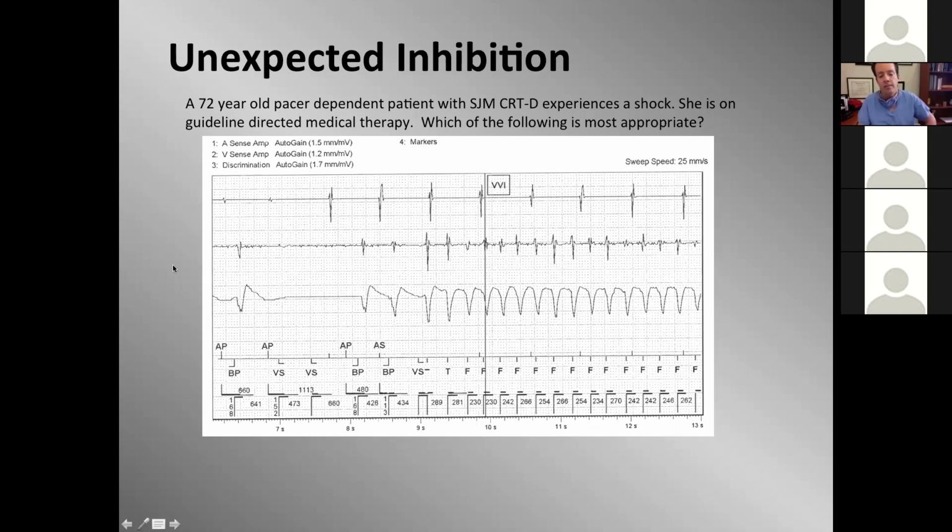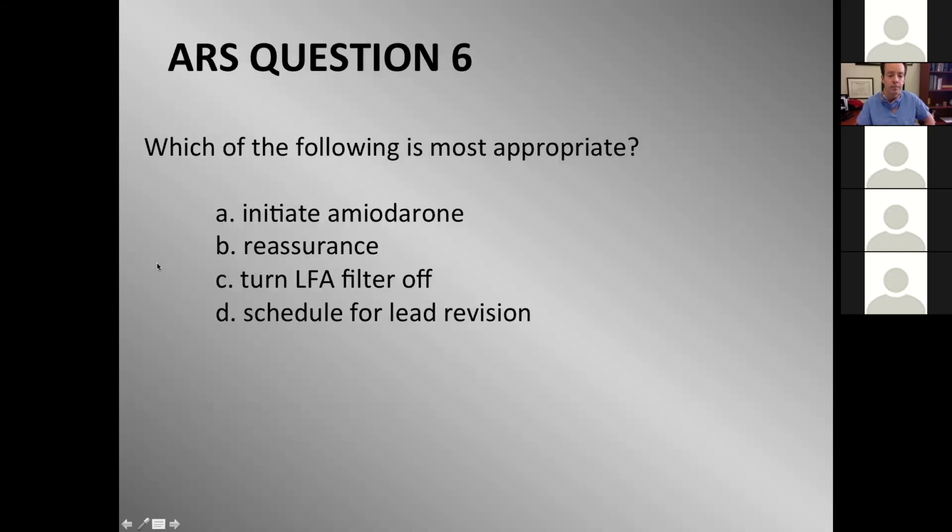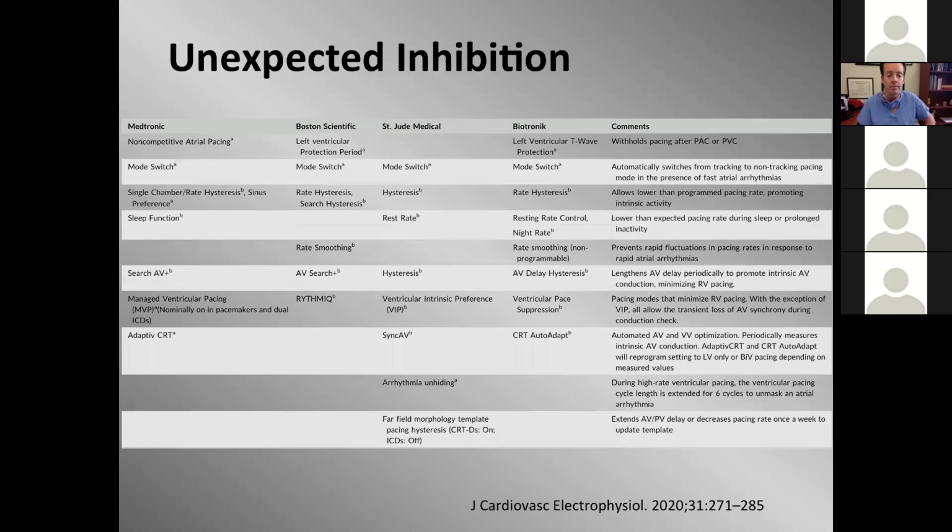So the LFA filter nominally at our institution is turned off because we've seen this too many times. We believe these are from phrenic myopotentials, but we can't prove it. But you have to know about it in St. Jude pace sense amplifiers. So the correct answer is turn LFA filter off.